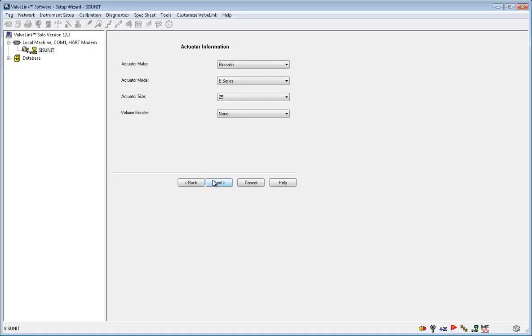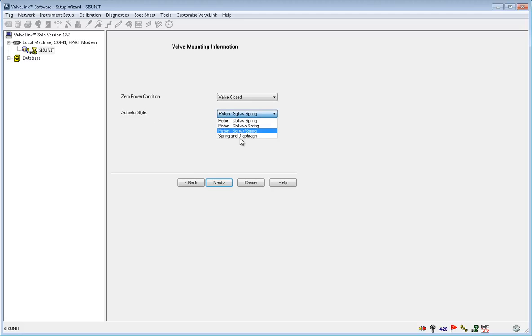The actuator information is next. Select your actuator make, model, size, and what kind of volume booster it has, if any. Mine is an Elomatic E-Series. It is a small 25 size and without any volume booster. So click Next to get to the valve mounting information screen. Choose whether your valve will open or close in a zero power condition and choose the actuator style. My valve is fail closed with a single piston with a spring actuator. Click Next once you've chosen your options.